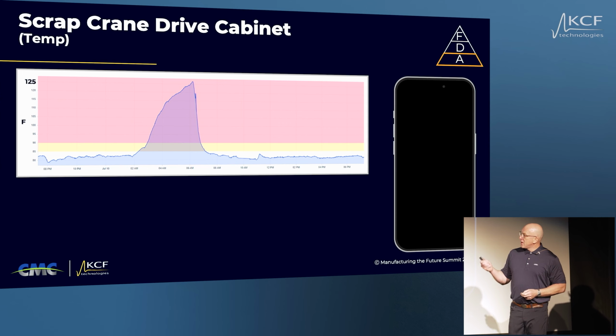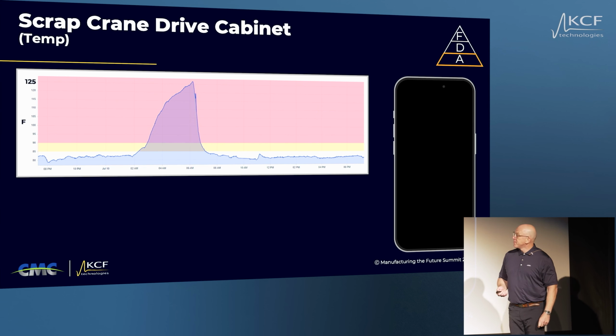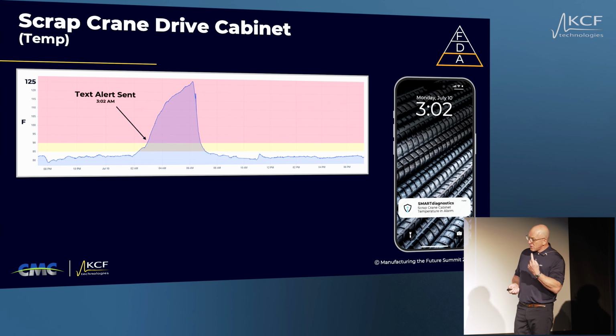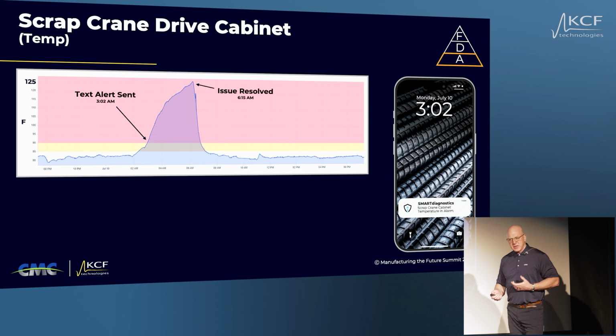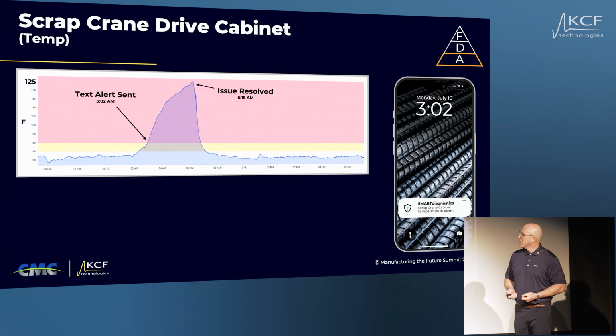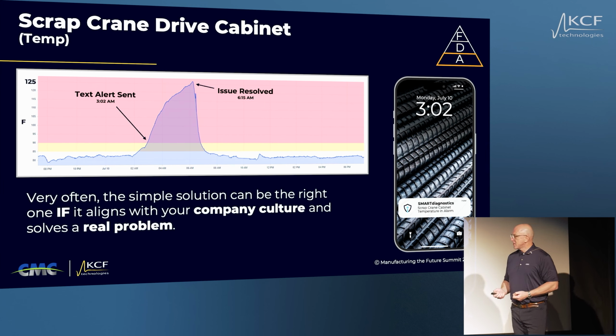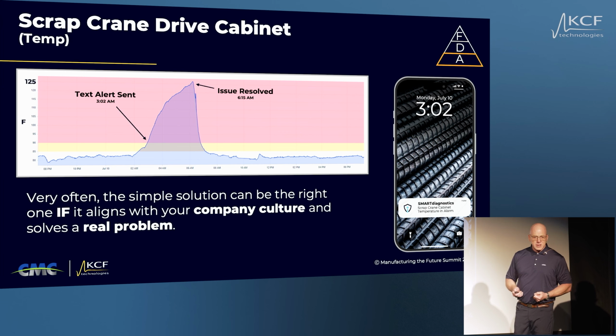So we employed a temperature sensor in the drive cabinet, and we got an alert this particular morning at 3:02, running on one drive. We got an alert at 3:02 via the cell phone app. And by 6:15 a.m., we were able to send one of our shift electricians up on the crane without interruption to figure out what was going on with the HVAC system up there, reset the HVAC, hence keeping the VFD that was running the crane cool. So very often the simple solution can be the right one if it aligns with your company culture and solves the real problem.